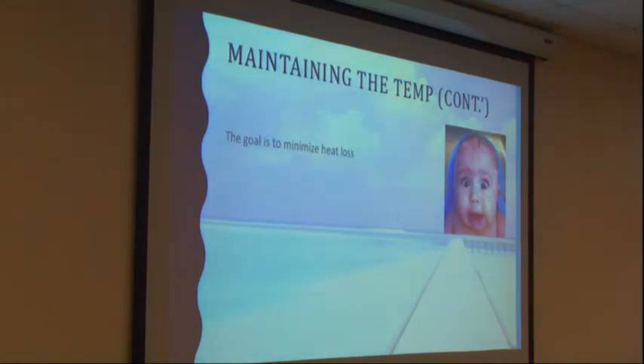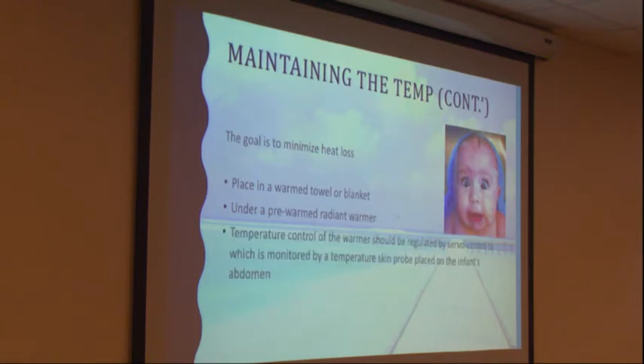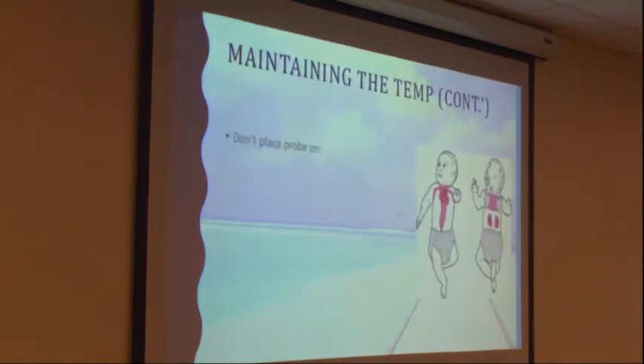Your goal in maintaining temperature is to minimize heat loss. Ways to do that include placing a warm towel or blanket on the baby, and placing the baby under a pre-warmed radiant warmer. The radiant warmer is temperature controlled - it should be regulated by servo control, with a probe monitored by a temperature skin probe placed on the infant's abdomen. It's really important that everyone knows how that works and how to place the probe, and where not to place it.